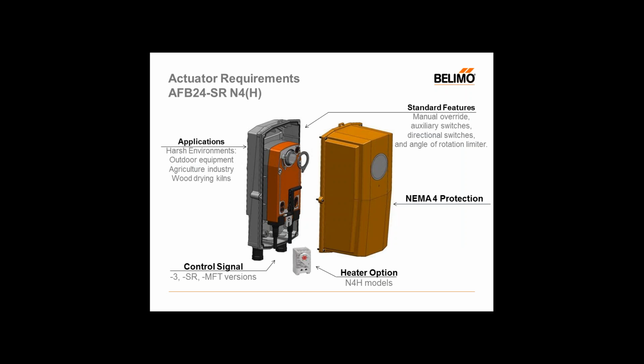Now, in terms of the type of installation or where it's being located, the actuators could come as a standard NEMA 1, which is basically for indoor use, or NEMA 4. So we highly recommend to look deeply into your application and see what is required of our actuators. Depending on the location, say it is exposed to the outdoor environment, NEMA 4 housing or some kind of weather shield is highly recommended. As depicted here in this slide, we do offer the AFB24SR as a NEMA 4, which is shown with the N4 suffix, which is basically the actuator within a NEMA 4 rated clamshell. This allows for outdoor installation if necessary.